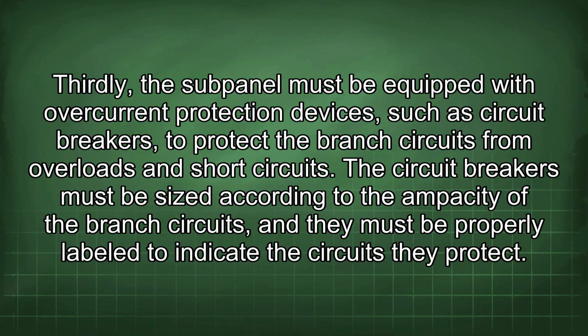Thirdly, the subpanel must be equipped with overcurrent protection devices, such as circuit breakers, to protect the branch circuits from overloads and short circuits. The circuit breakers must be sized according to the ampacity of the branch circuits, and they must be properly labeled to indicate the circuits they protect.